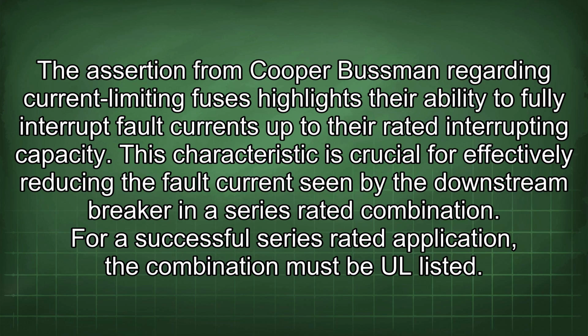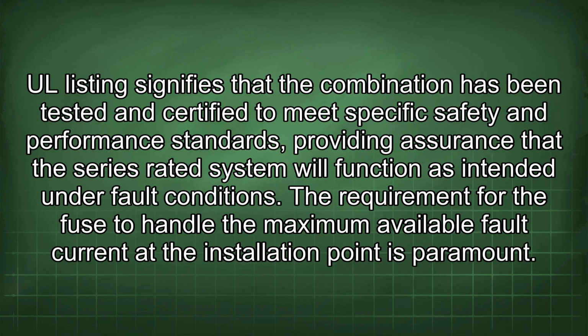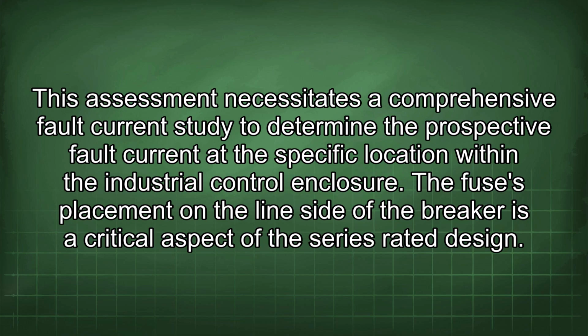The assertion from Cooper-Bussmann regarding current-limiting fuses highlights their ability to fully interrupt fault currents up to their rated interrupting capacity. This characteristic is crucial for effectively reducing the fault current seen by the downstream breaker in a series-rated combination. For a successful series-rated application, the combination must be UL listed. UL listing signifies that the combination has been tested and certified to meet specific safety and performance standards, providing assurance that the series-rated system will function as intended under fault conditions. The requirement for the fuse to handle the maximum available fault current at the installation point is paramount. This assessment necessitates a comprehensive fault current study to determine the prospective fault current at the specific location within the industrial control enclosure.